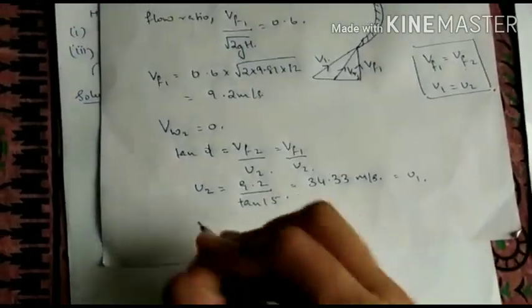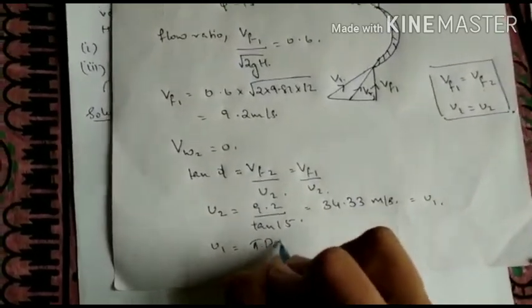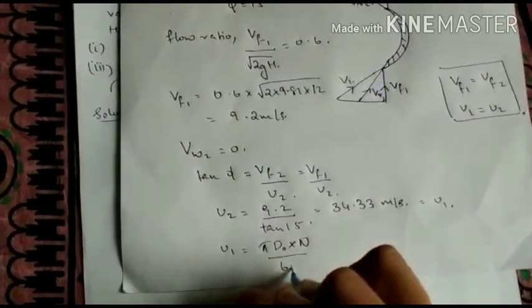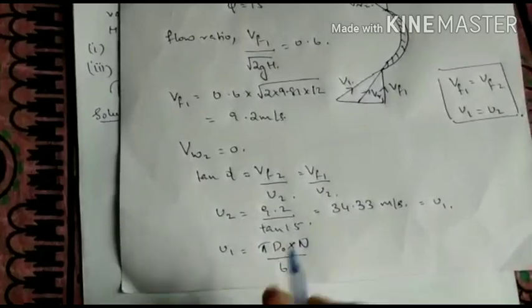Now from the relation U1 is equal to pi D0 into N by 60. From this everything is given except D0. So we can find D0. From this we will get it as 6.55 meters.